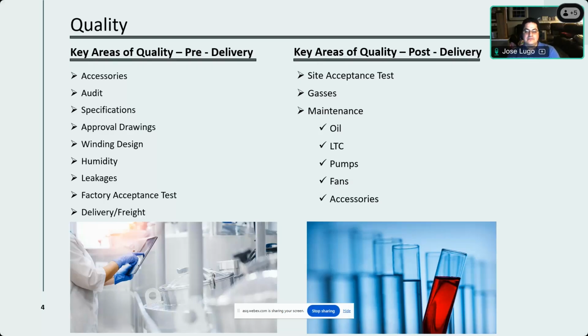Then there's the LTC. We want to test that as well and maintain it, because that's the only mechanical part of a power transformer. Everything else is static. The LTC has a mechanism that moves through some steps, and that's the only real moving part. Eventually it will fail because it has movement. If you maintain it, you can anticipate when you need to de-energize everything and replace it, or replace the LTC only.